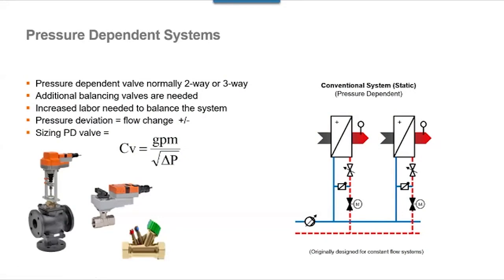Let's talk about pressure dependent and pressure independent valves. In a pressure dependent valve system, you have a balancing device, you have a control valve. It could be a 2 or 3-way valve. You have, I'm going to say, increased labor to balance the system. You have to go out and balance the system. As we saw in the previous slide, when pressure changes, flow changes. All going back to the whole concept on how we're sizing and controlling these valves.